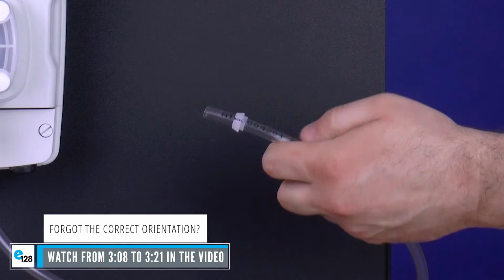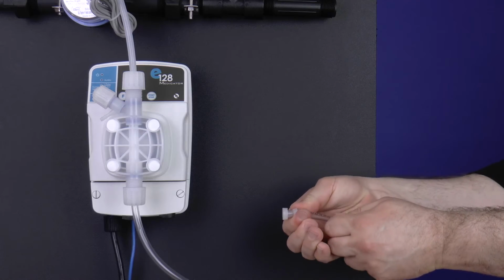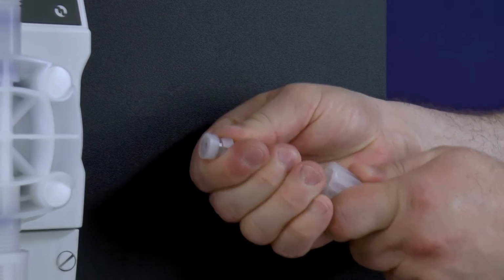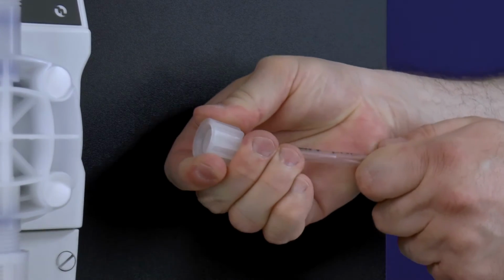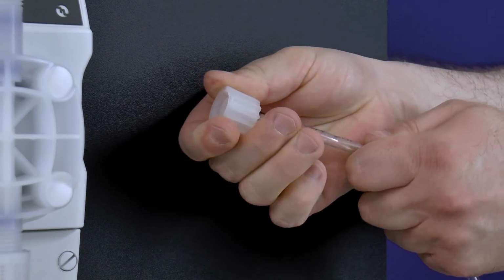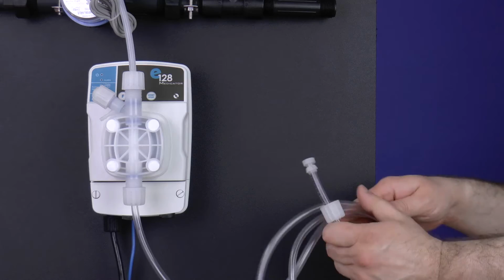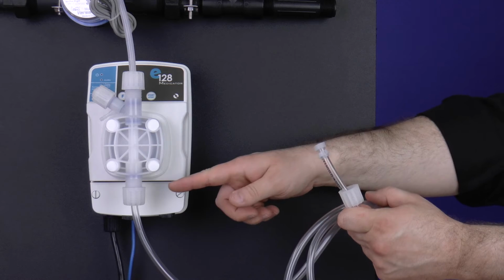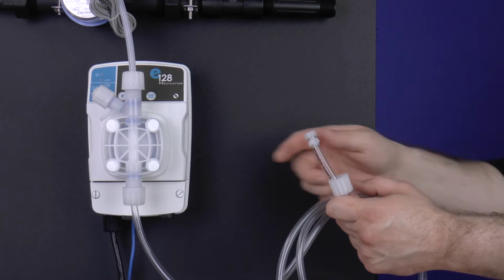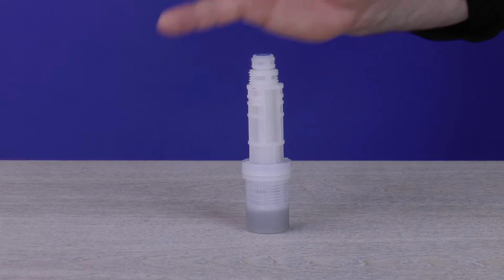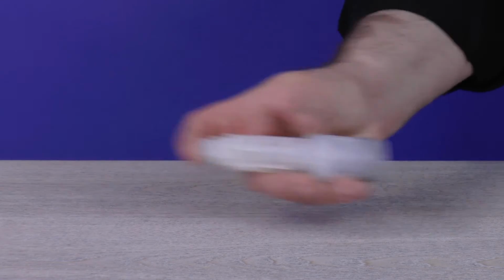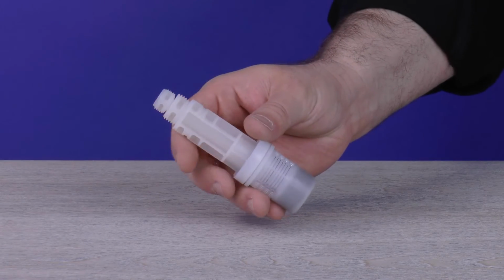Slide the tube connections onto the loose end of the PVC suction tubing and be mindful of the orientation for the tubing connections. Push the collar and nozzle together as close as possible. Pull the tube nut toward the nozzle to compress the collar and nozzle tight together, forming a ferrule connection. Let the PVC suction tubing along with the foot filter tube nut, collar, and nozzle hang from the pump head. Grab the foot filter and shake it back and forth. You should hear a ceramic ball moving freely inside.